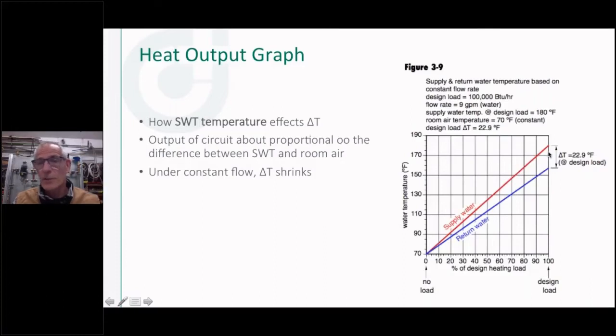So I'm just turning the thermostat on for the first time, the house is starting to come up to heat, and I've got this kind of delta T. What's going to happen is I start catching up with my heating load. Down here, as my heating load starts being covered, you can see the delta T is going to close, getting smaller and smaller until it gets down to 0 when the heat load is covered. This is a normal operating condition for a hydronic system where we're maintaining a constant flow rate. I'm not varying the flow rate, and I'm supplying a certain temperature, and that delta T is going to close up as the heat load goes away.